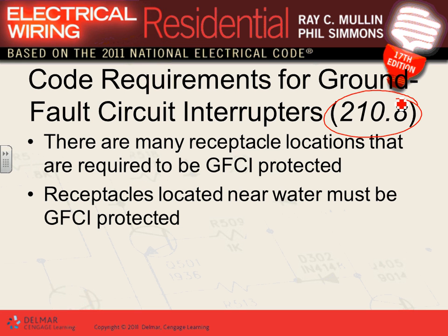So these are the locations, but let's focus on the residential today. Any comments, guys, about the locations in residential where you need a GFCI? Did we forget any of them? Bathrooms, countertop, kitchen within 6 feet of a sink, unfinished basement, garage, outdoor. These are the locations where you need the GFCI.